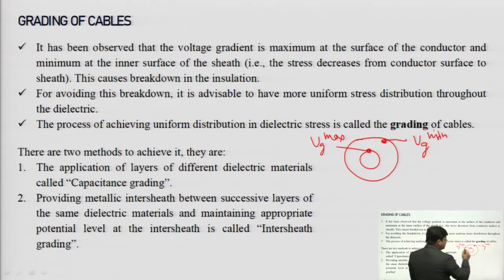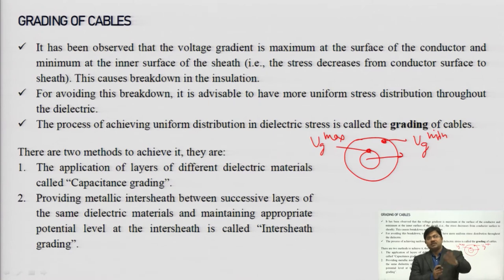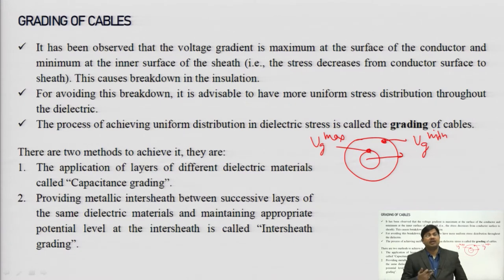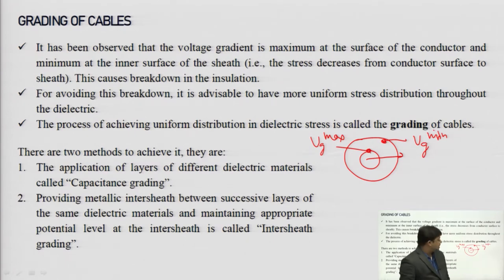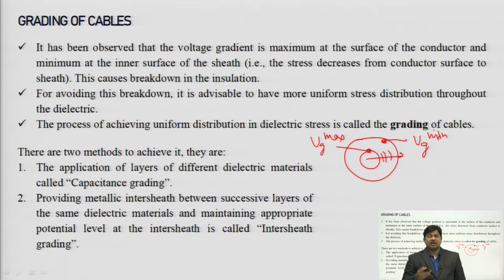If you move radially from the core toward the insulation, the voltage gradient decreases. This means the stress decreases from the conductor surface to the sheath surface. Due to this voltage difference, there is a possibility of leakage current, and because of that leakage current the insulation may break down, causing problems. To avoid these breakdowns, it is advisable to have a more uniform stress distribution — the more uniform the voltage distribution, the fewer the breakdown chances.